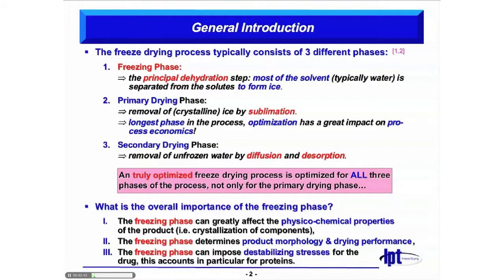The next step would be the primary drying phase, where we remove the already crystallized ice by sublimation. This is the general principle of freeze-drying. The longest phase is the primary drying phase, and therefore typically people optimize this phase to get more economic process conditions, to cut cycle time and save money.